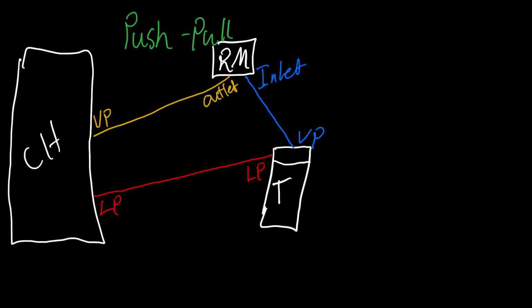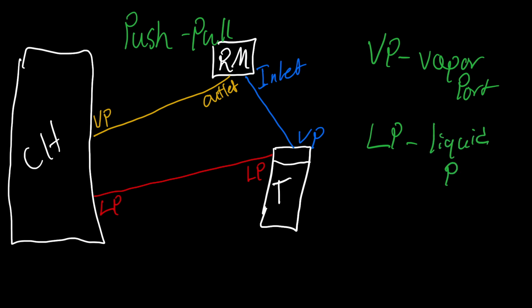So our cycle of recovery, we're pulling vapors off of the recovery cylinder, which is keeping our pressures down, our temperatures down, but that's also allowing a low pressure point for all the liquid refrigerant in the chiller to flow into our tank. And by pulling the vapors off the top of the tank, we're then pushing them back into the chiller, which is keeping the pressure up in the chiller as well. One of the great things about this method is the chiller itself should never go into a freezing condition in saturation, so our saturation should never get that low while we still have liquid in the chiller, and that's really the most critical part. We don't want our saturation to be in a freezing temperature if there's still liquid refrigerant.